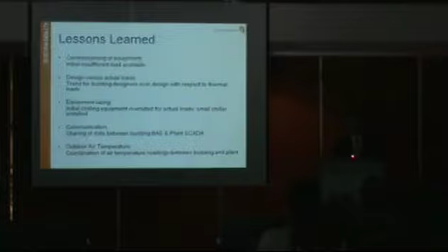So lesson learned: commissioning is important, design versus actual load. In a LEED certified building, we discovered the best projected load may not tally with the actual thermal load requirement. Why is it important? Because in designing for phase 2, phase 3, and phase 4, we have to inform ourselves what is the actual thermal load for that building, which leads to a much leaner design in the future and saves a lot of costs.